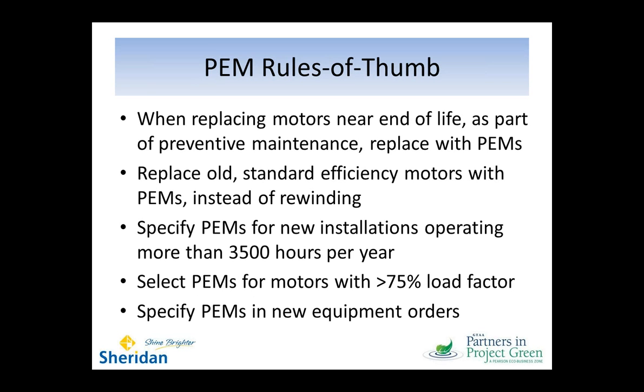And if you're looking at premium efficiency motors, here are some rules of thumb, just little guides you can use. When you're replacing motors that are near their end of life, like in the preventive maintenance program, or you've gone out and looked proactively, those are the chances to put in the premium efficiency motors. You're buying new. You can also look around for the old standard efficiency motors, so 15 and 20 years old. Don't rewind those. Get a premium efficiency motor in there and actually just get the right energy efficient solution in right away.